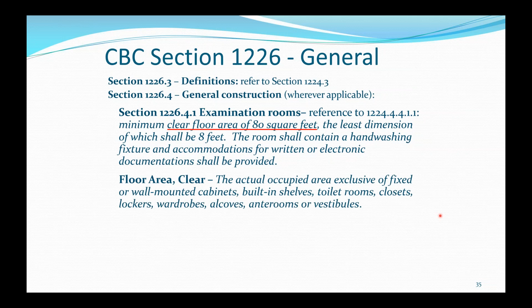Again, these are minimums. I know in a lot of the older clinics you might be at 7'11" or 7'10", and we've provided some guidance in the checklist, which we'll cover later, to allow a little leniency if you're that close. When OSHPD does a review of an existing clinic space, we wouldn't penalize them if they're that close. So we're trying to provide some guidance to the authorities having jurisdiction. The rooms are required to have hand washing fixtures and a counter for writing. And the floor clear area is exclusive of fixed or wall-mounted cabinets, so it has to be actual floor space.